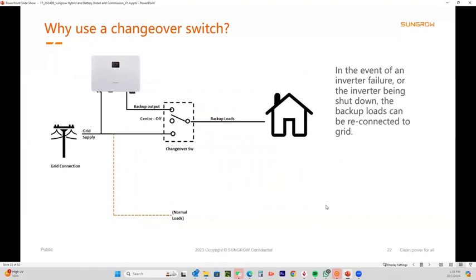Changeover switch. We now include changeover switches. Obviously it's a 3-pole changeover switch on the 3-phase models. This is simply because there are a couple of reasons. One is that in places like Victoria, for example, when you install a system, you're not allowed to actually switch it on until it's been inspected, I believe. So what you do with the changeover switch is you install the system, make sure it's working, and if you've got the whole house on backup, there's going to be no power because the inverter is switched off. So you just switch this through the contacts to the center off and on to grid. So the customer is basically still connected to grid, and you let them know that when the system is switched on, they switch this back up to the inverter like that.